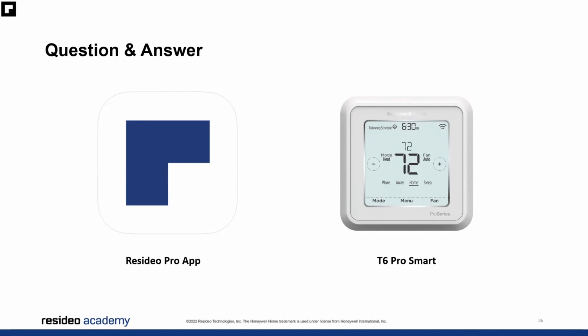Sure. Thanks, Isaac. Historically, what we've viewed as residential thermostats don't cover some of the more advanced features, such as droop or finishing with higher heating or cooling stages, some of those more advanced features that would tend to throw off the average DIYer. In general, you can say that trade thermostats, or professional install thermostats, will handle sensors, dual fuel applications, and IAQ, so heat, humidifiers, dehumidifiers, and ventilators.